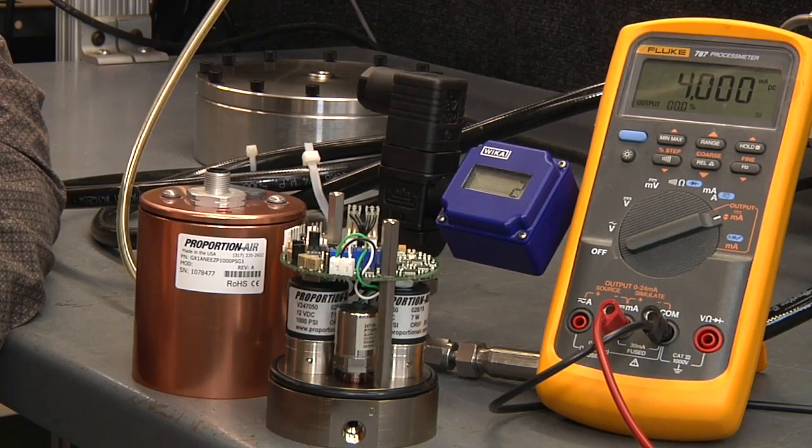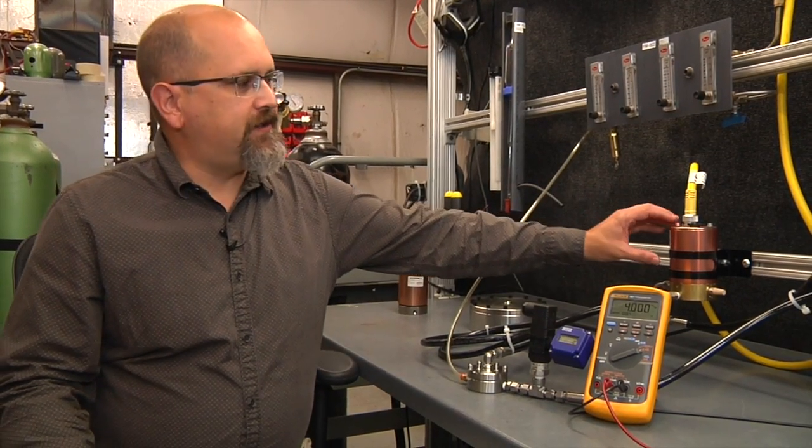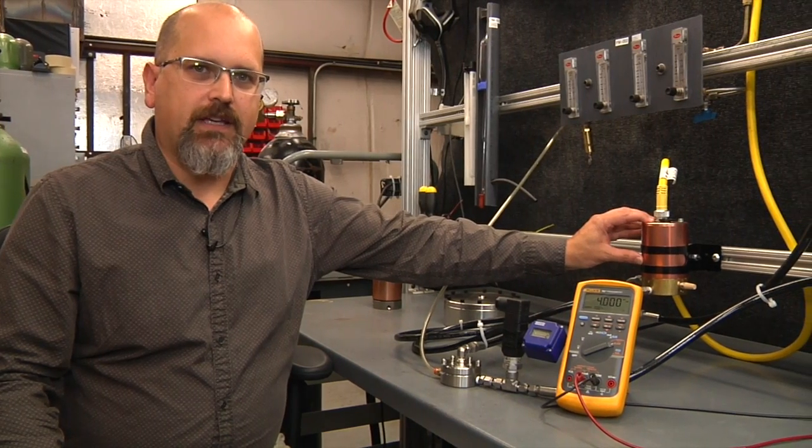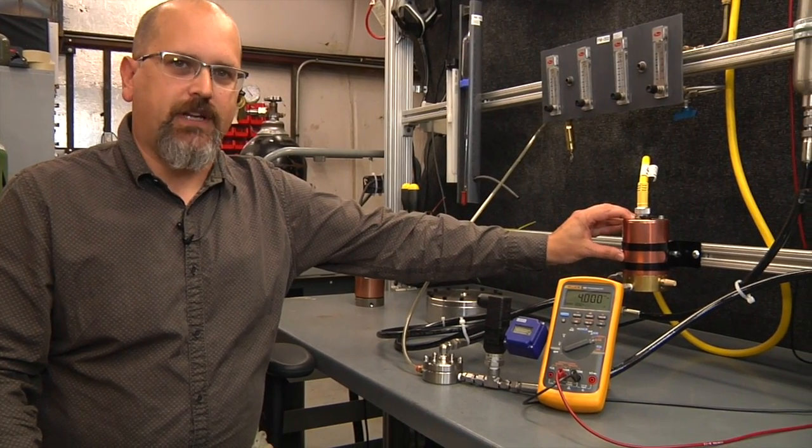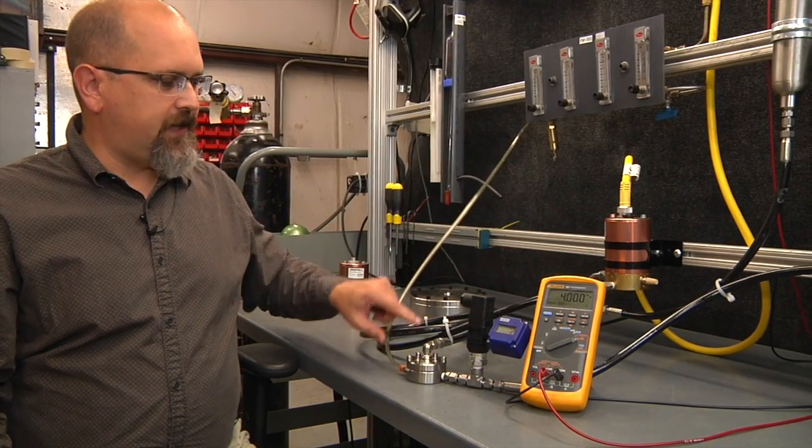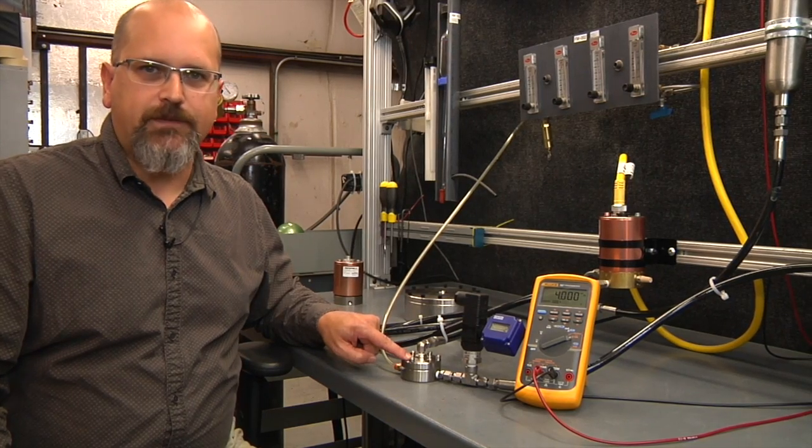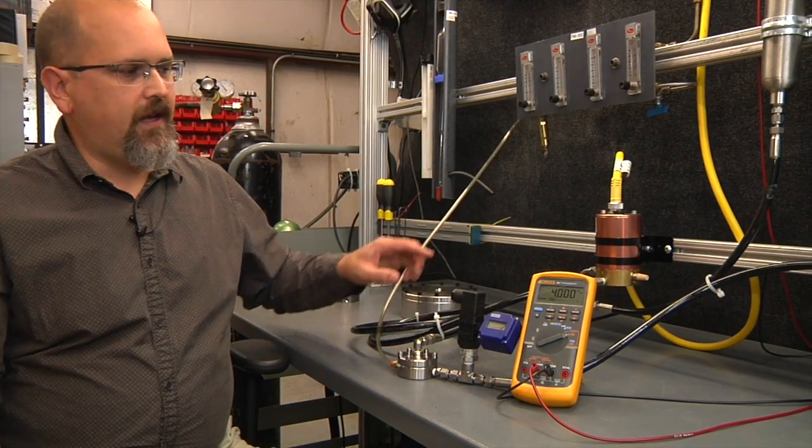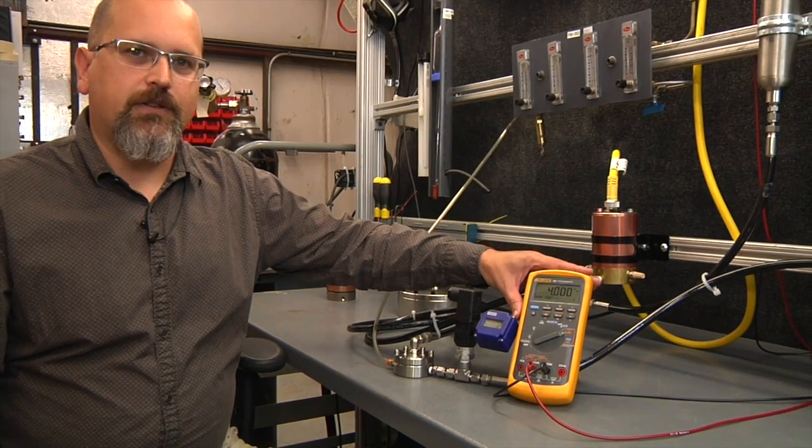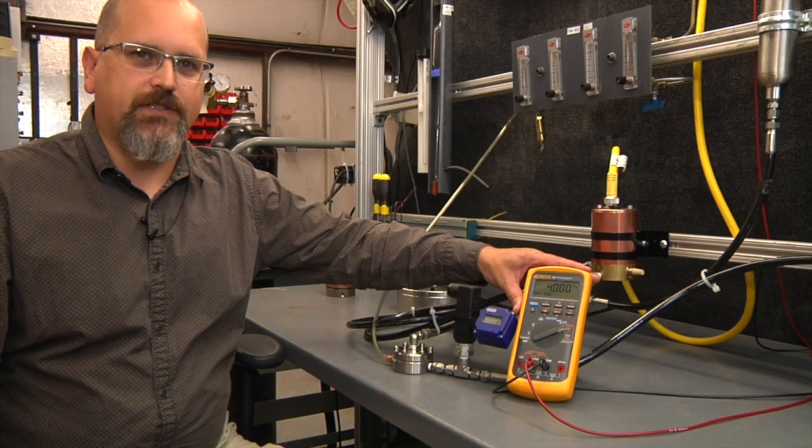For our demonstration today, we'll be using a 0 to 1000 PSI GX Series from Proportion Air to provide a 0 to 1000 PSI pilot signal to this precision Equilibar LF Series back pressure regulator. We'll provide a command signal to the GX using this Fluke 787 process meter.